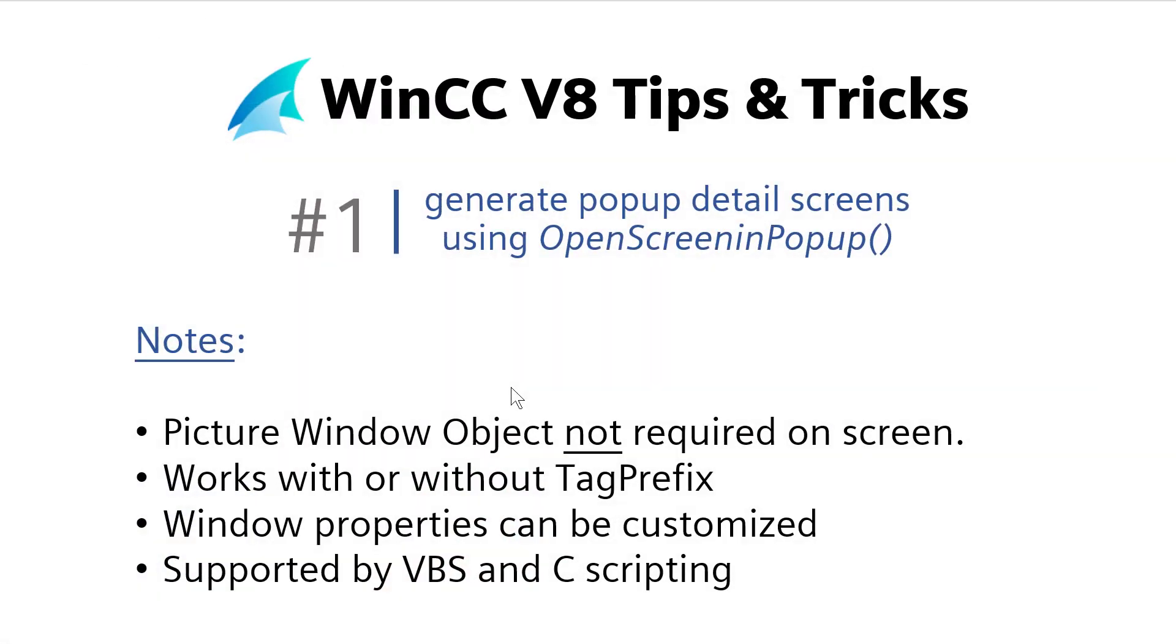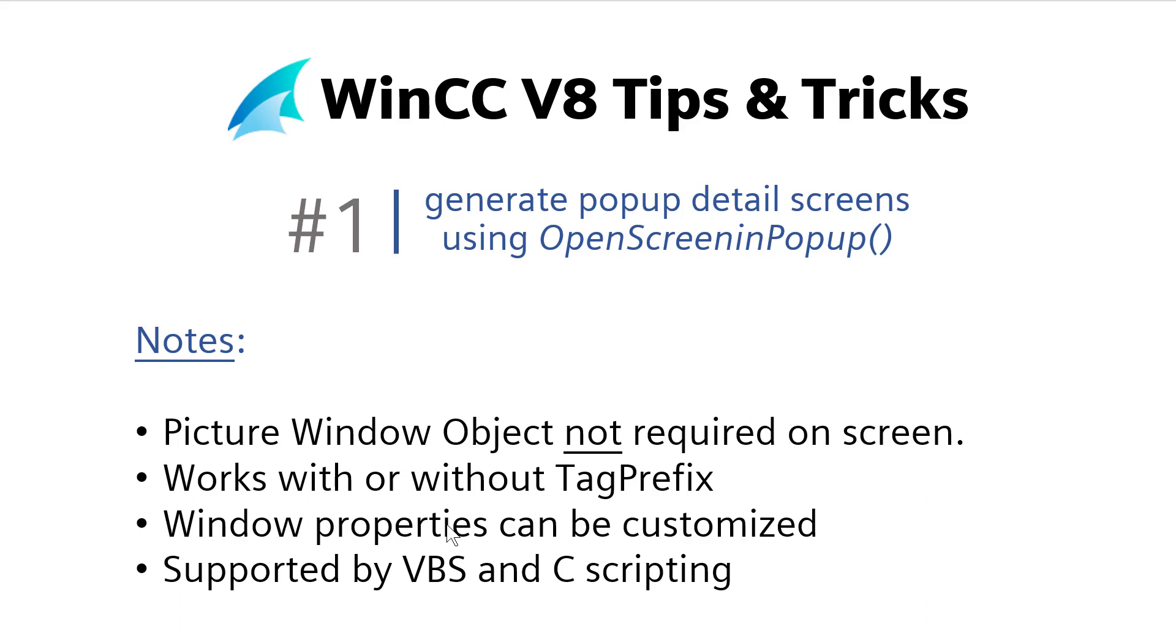So when using the OpenScreenInPopup function, you don't have to have a picture window object on the screen. It also works with or without tag prefix, which we also covered in the step-by-step series. You can get a handle to the object in runtime, and so you can customize the windows properties like the title script and things like that. There is an OpenScreenInPopup function supported in visual basic scripting as well as C scripting. So if you're interested, stay tuned. I'll show you how to do this.